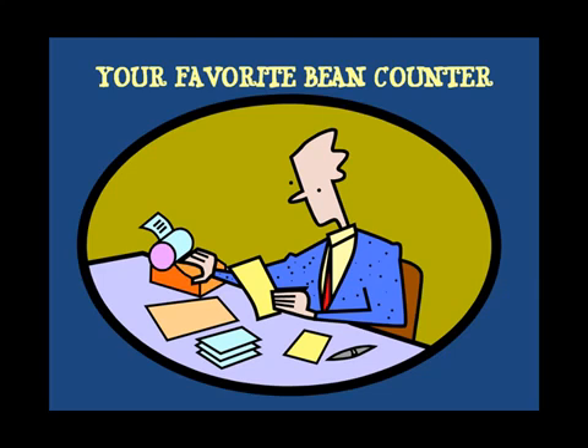The moral of the story is this: if the logic in a PLC checked the status of every input that came up in a rung of logic as they appeared in the rungs of logic, and in turn updated each output at the end of each rung, there isn't enough time in the day to run the scan of the program. So, we collect the status of all of the inputs in one motion, execute the logic against the images of the inputs stored in the input file 1, write the conclusions to the output images stored in output file 0, and then we deliver the updated status of the output file to all of the output modules in one single effort. How clever we are.